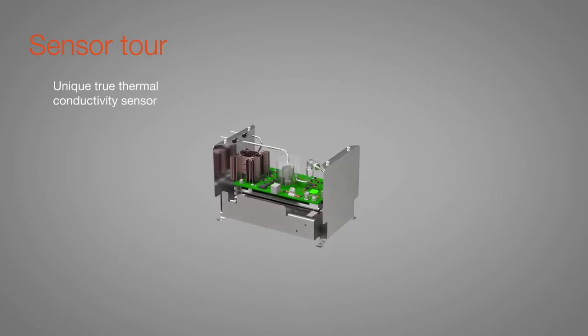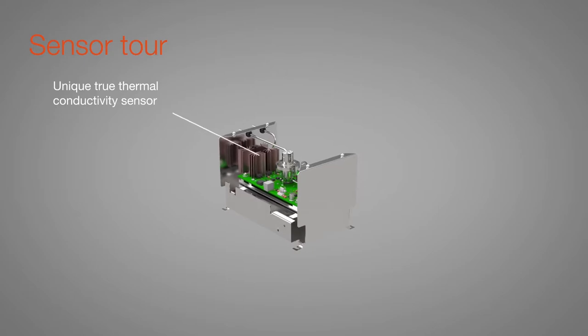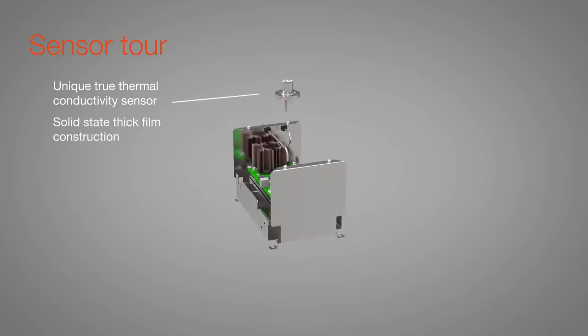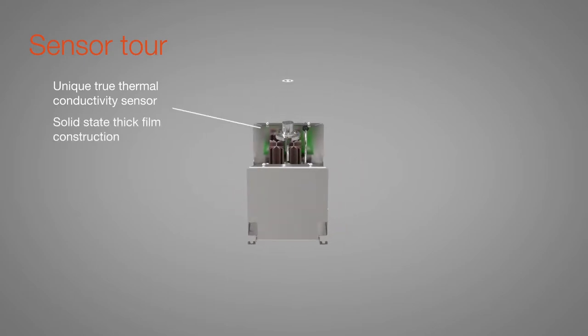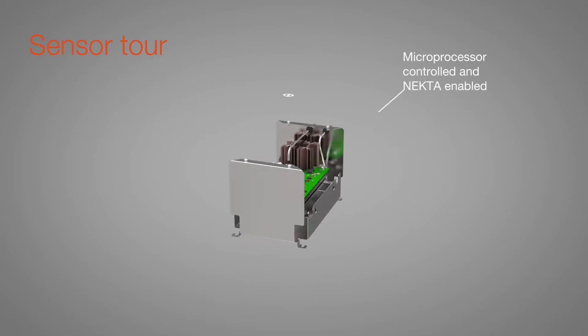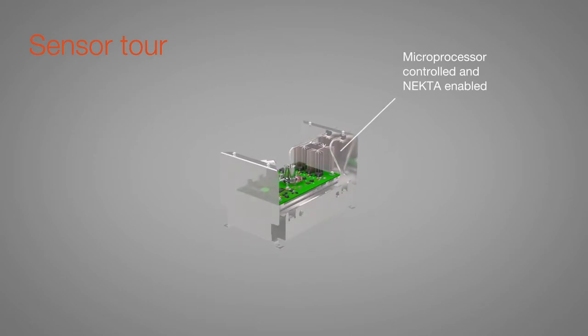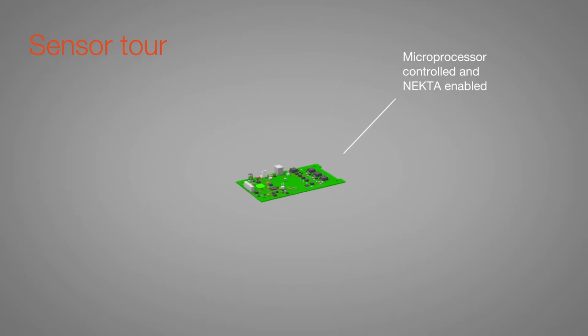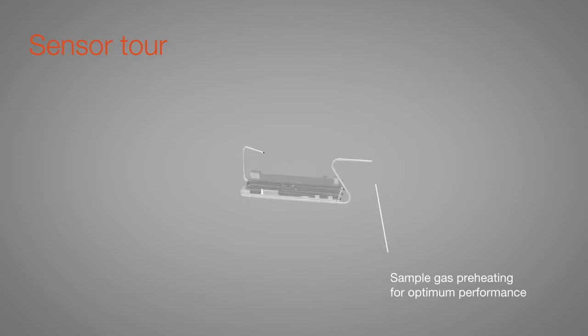Both measure and reference elements are held under isothermal conditions within the sample gas. It is microprocessor controlled. The sensor also benefits from highly reliable solid-state thick film construction with the sample gas preheated to further optimize performance.